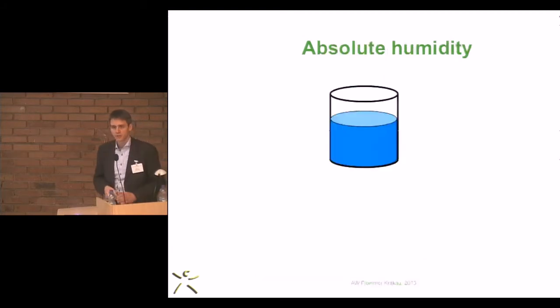Now, what is humidity? We heard about humidity in the incubator already, and I was saying to Jerome that if you see a lot of rain out at the walls of your incubator, something is wrong with the environmental temperature, and your humidity in the incubator is never what you want to achieve, because you're losing humidity once you see rain out. Now, in order to understand that, we go a little bit through the physics of humidity.